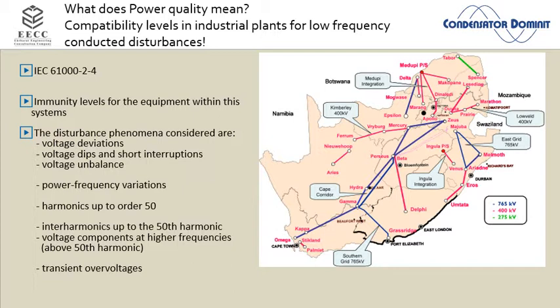Voltage quality or power quality means any deviation of the voltage in height is not wanted. Then there's the voltage waveform, it cannot be a perfect sine wave, that's also not wanted. When I speak about the voltage waveform, the IEC standards write about so-called harmonic voltage distortions. That is a very clearly defined frequency disturbing the net. Typically, for example, the 250 Hertz fifth harmonic voltage is a typical phenomenon. The standard also speaks about non-harmonic voltage distortions. That's everything which is not a multiple of 50, like switching frequency of some semiconductors in the grid, or resonance phenomena or similar. And there's also defined transient overvoltages. That's what the standard is dealing with, and that's what we are dealing with.